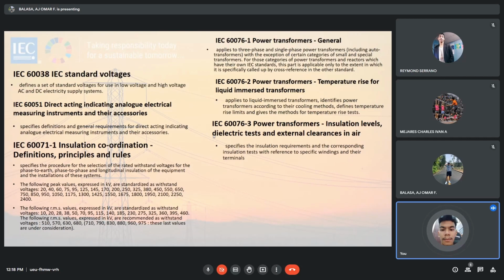Para naman sa mga water-cooled transformers, normal cooling condition for water-cooled transformers is a temperature of cooling water at the inlet should not exceed 25 degrees Celsius at any time or 20 degrees Celsius yearly average. If the operating water temperature is higher than this, then a lower temperature rise should be specified. Para naman sa mga air-cooled transformers, normal ambient temperature limits for power transformers are given dun sa IEC 60076-1.